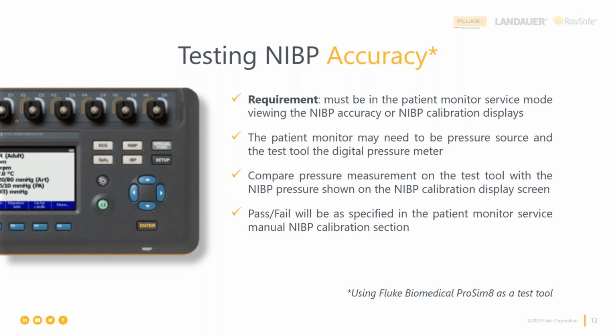So our patient monitor may need to be the pressure source, that's fine. And then whatever it displays on its calibration screen is compared against what we see on our test instrument, and they should agree within whatever the accuracy specification claimed by the medical device manufacturer. It's their spec, it's their design. We're using our test instrument to make sure that what they said is what that medical device actually does. That's what we're doing. So we're going to do this comparison, and it's either within the tolerance or it's not. So it either passes or it fails.